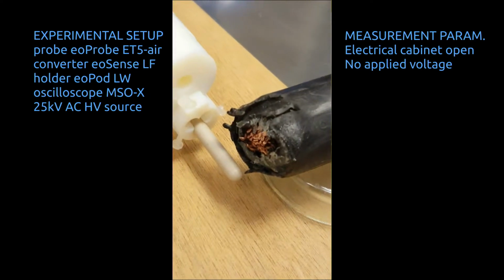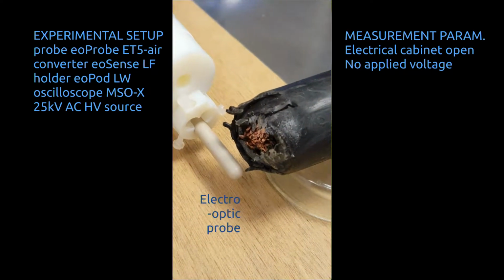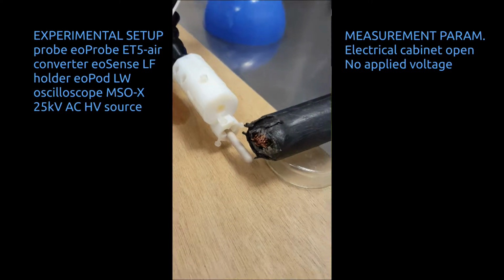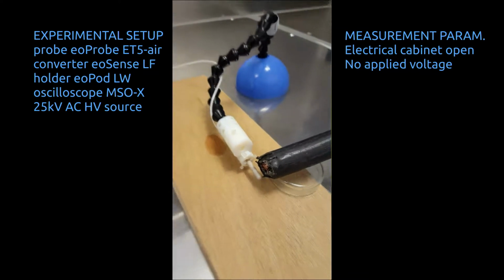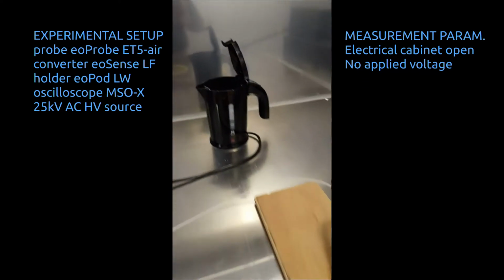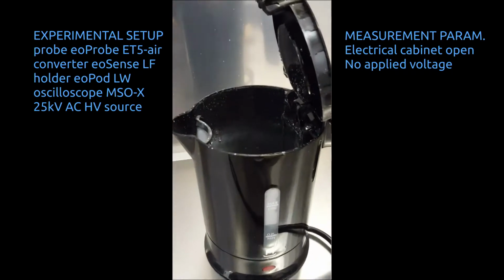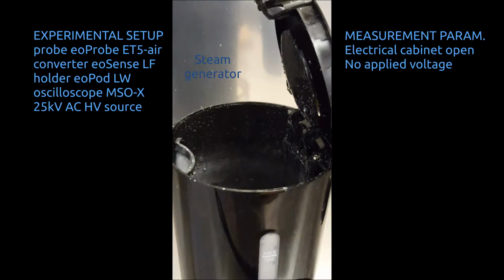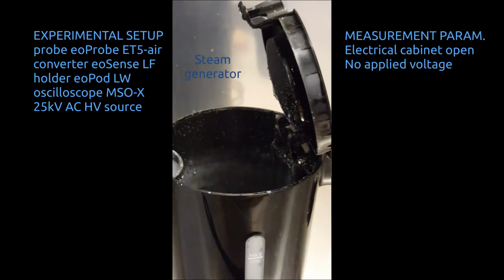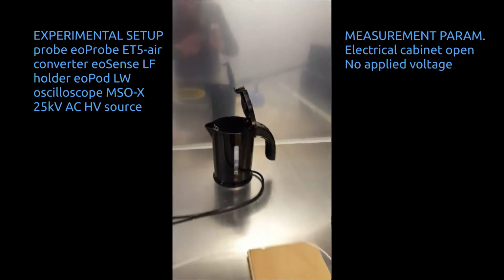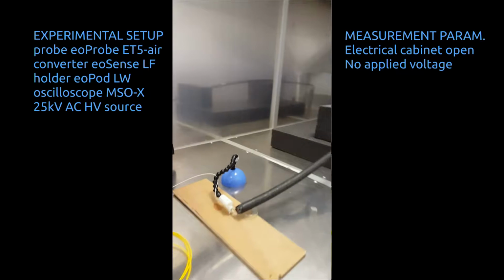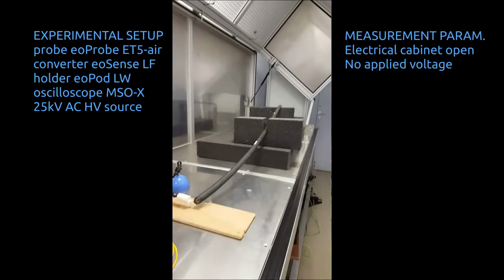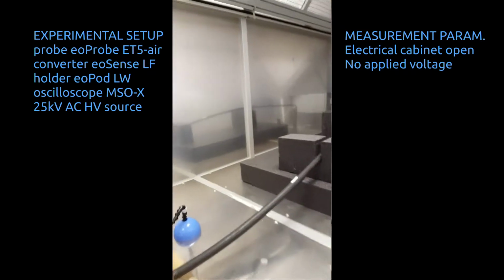You can see here the electro-optic probe positioned at the end of the high power cable. To initiate more partial discharge, we've used a steam generator, and before switching on the high voltage source, we need to close the electrical cabinet for safety.